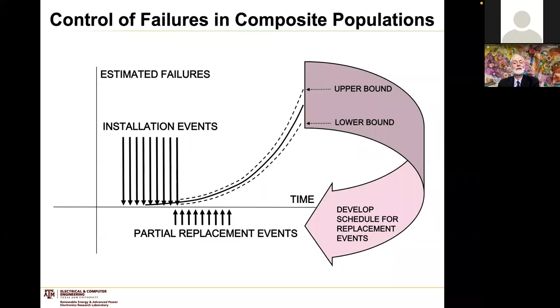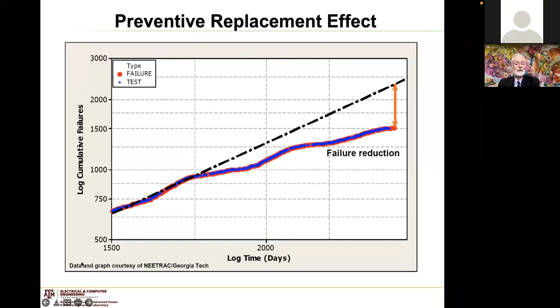With that information, we try to address the issue of a cable system which has many installation years and many partial replacement events, replacing aging portions of the cable. Then we try to calculate for that compound system the distribution, upper and lower bound, of the number of failures that are being expected. Usually that number is the driver from which to calculate future replacement events. So the net effect should be the net failure reduction compared to the growth of failures that would be happening without any actions. This is typically what the data that utilities provide look like.